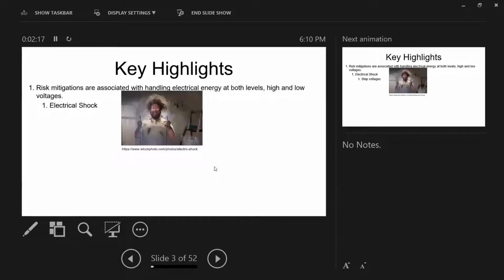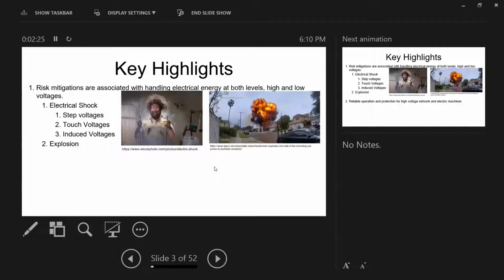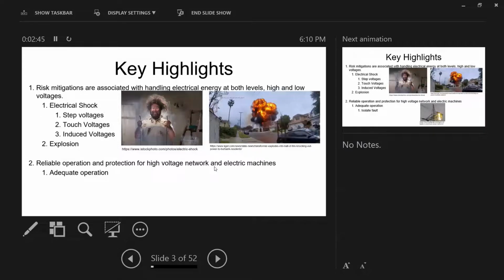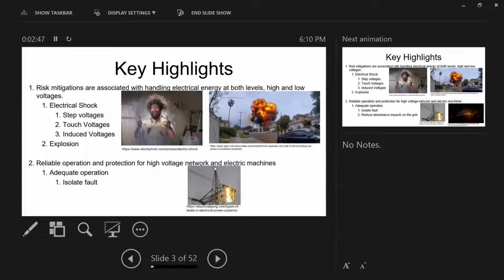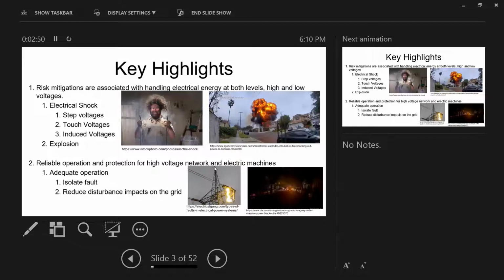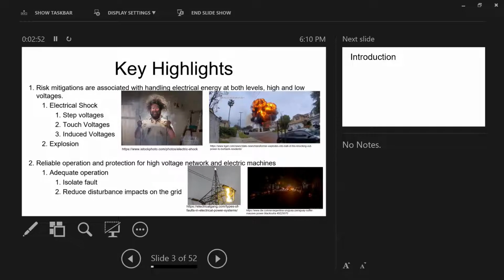Number one, you can get electrocuted by step and touch voltages. Number two, I will have an induced voltage and then I could get an explosion. This is risk mitigation against electric shock and explosion. And the second key highlight is reliable operation and protection of the system, because you always want adequate operation. You want to be able to isolate the fault, and you want to be able to avoid any blackout.